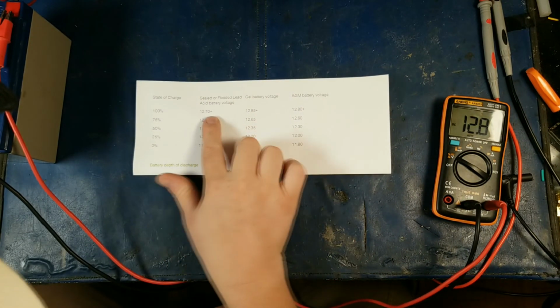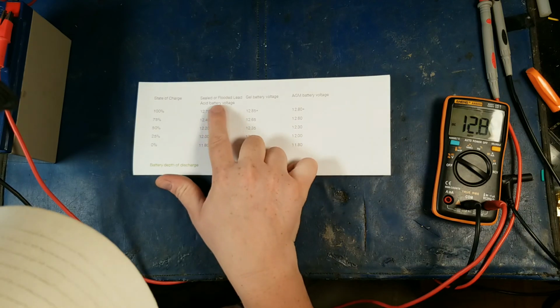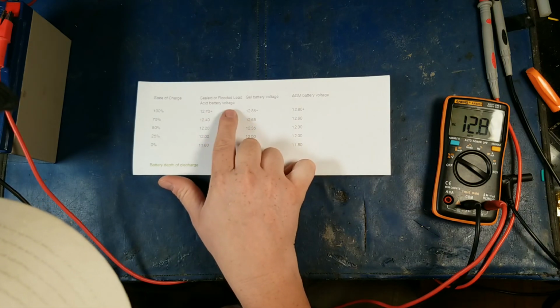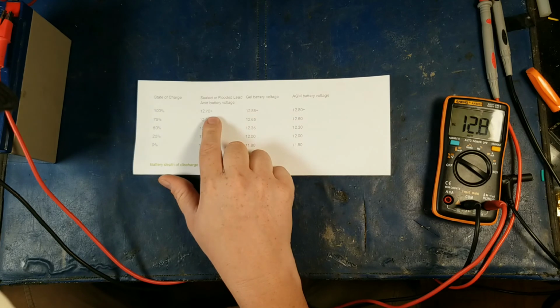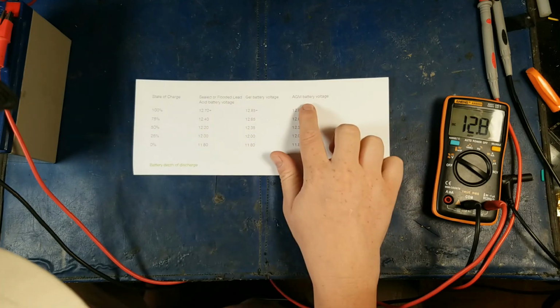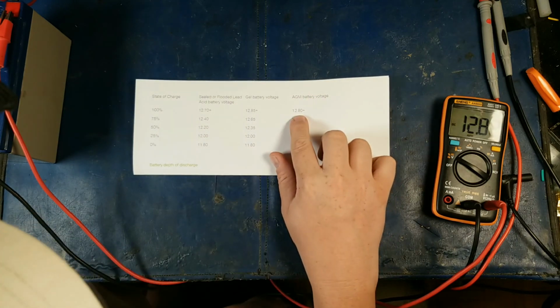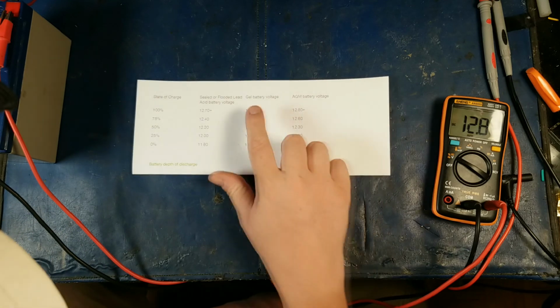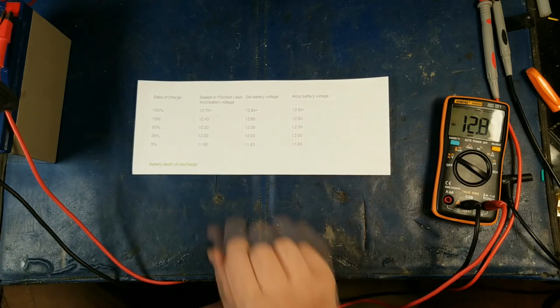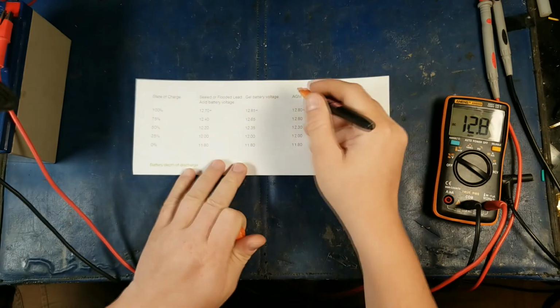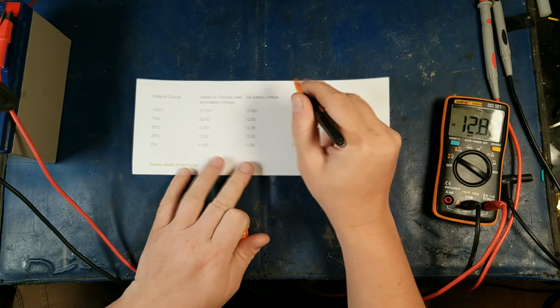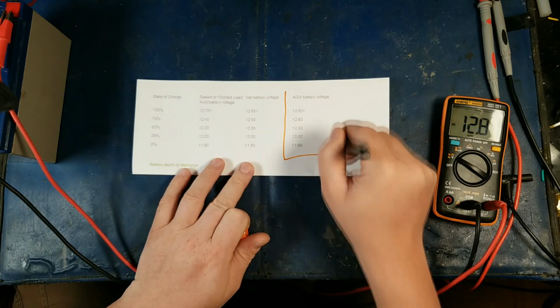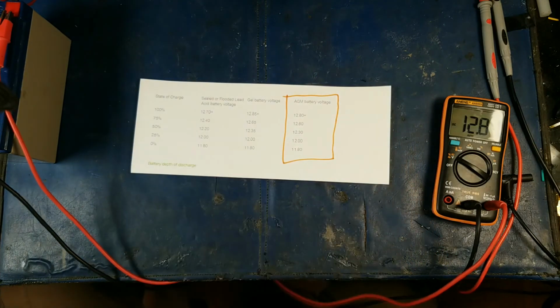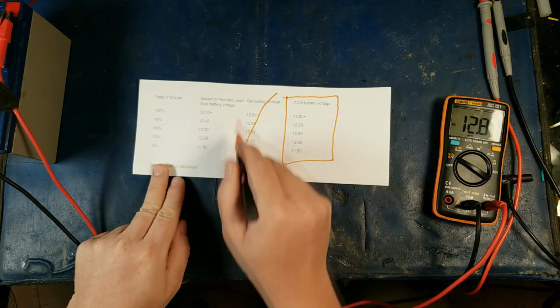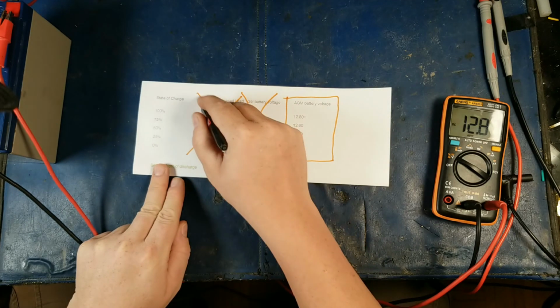Charge state at 12.7 plus for sealed or flooded lead acid batteries means it's at 100%. AGM batteries, full charge is 12.80 plus, and gel batteries is 12.85. We are specifically going to focus on the AGM because that's what most of your batteries are going to be in your tower assemblies.